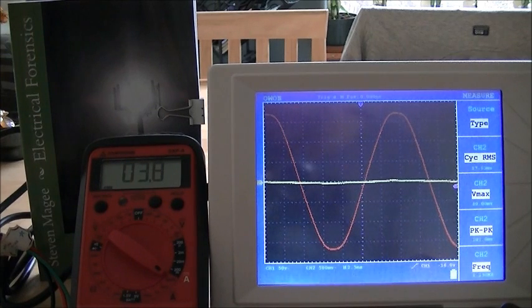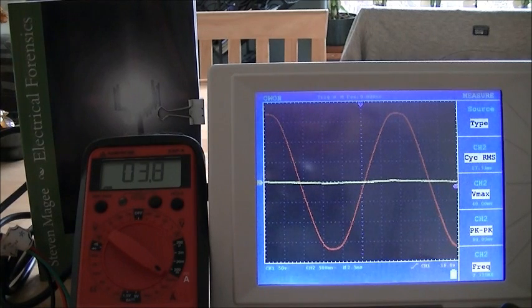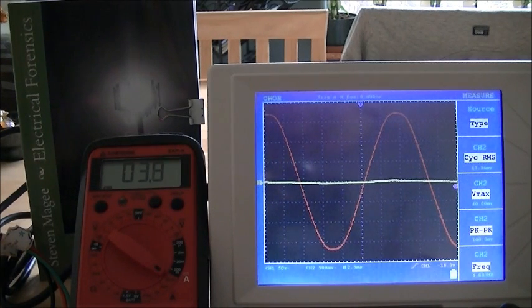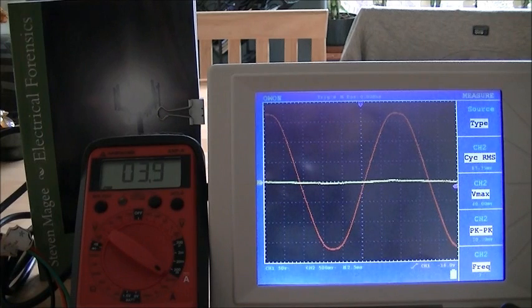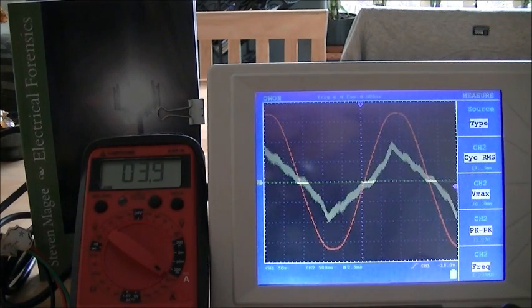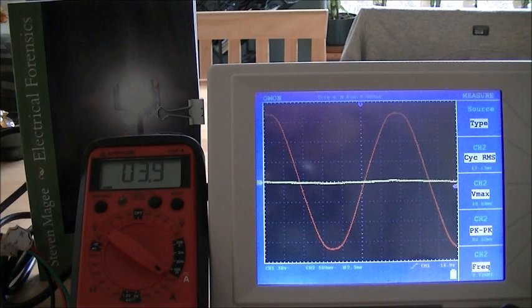You can see it's now reading 3.8 milliamps and last year I was getting about 60 milliamps when the ground rod was new. I think the reference ground rod in the back garden doesn't have a very good connection right now for passing current. If I take it off you can see we get our waveform back. I put it back on, we lose the waveform and we start passing 4 milliamps.